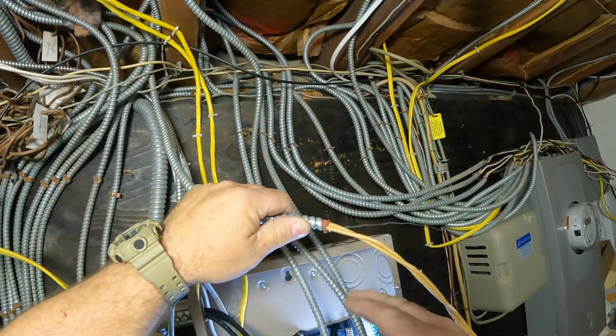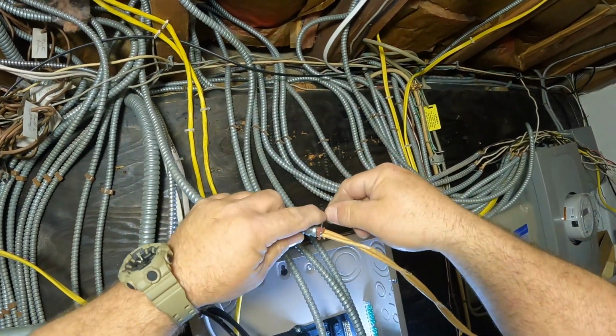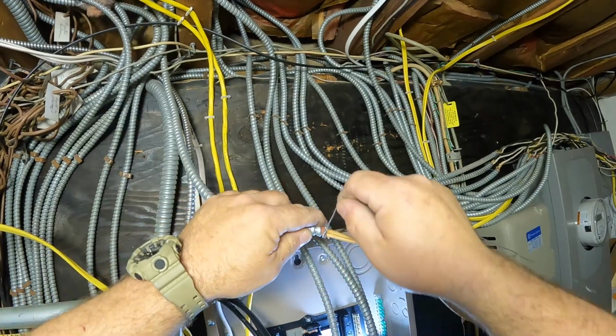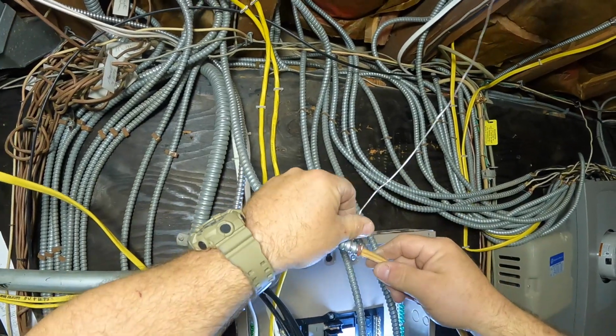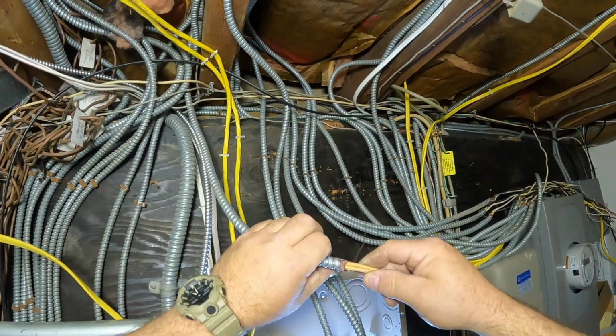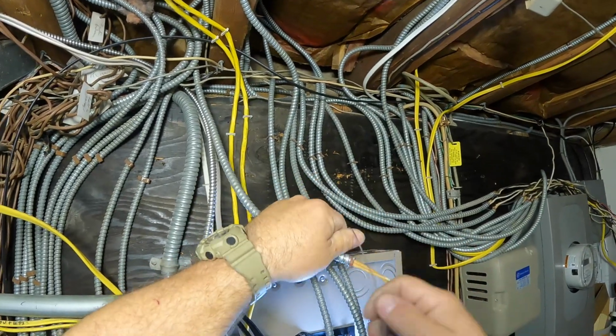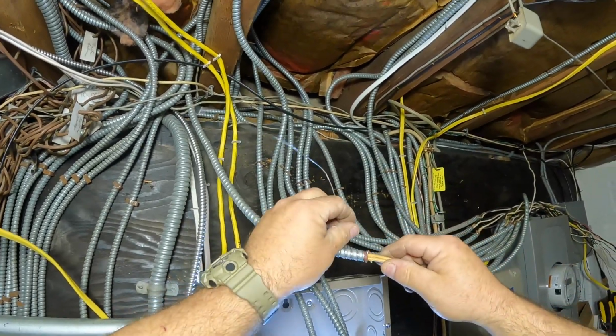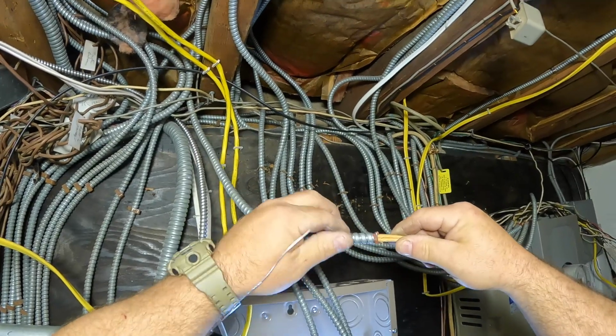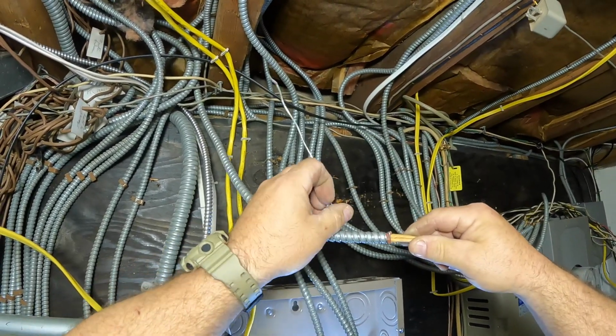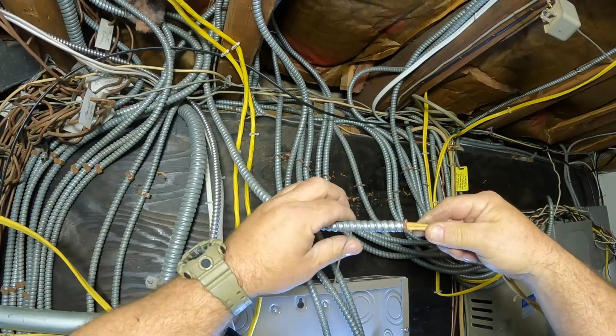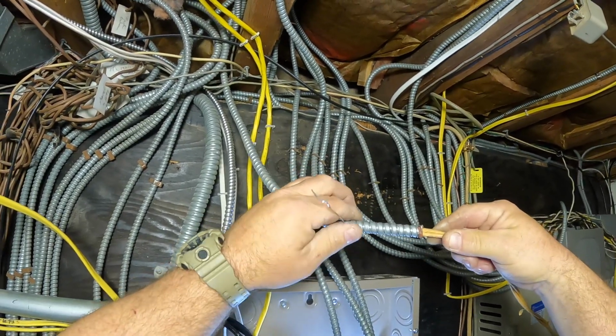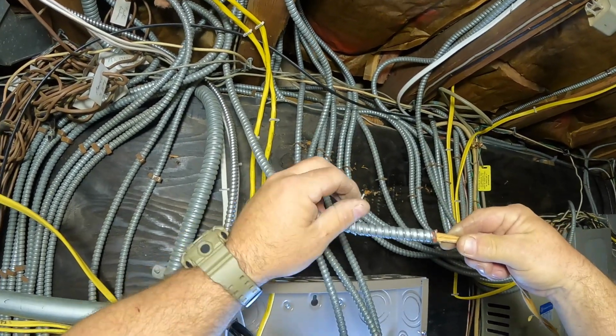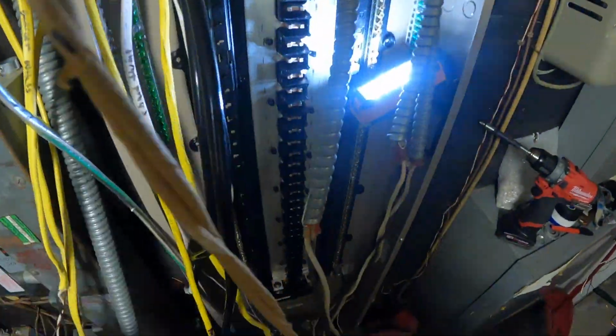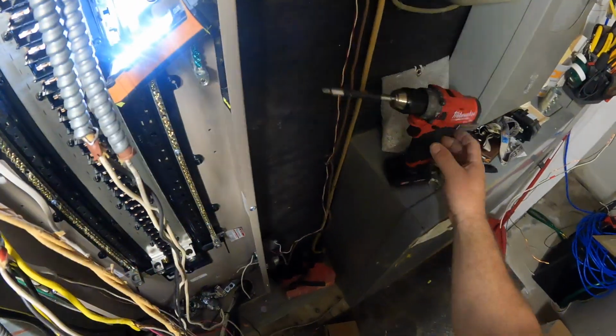So this one's a BX cable, and you see I'm putting what's known as a red head. The real term is an anti-short. And what that does is it safeguards the conductors from that sharp cut you just made with the cutters, from nicking the conductors. On armored cable, you are required to put the anti-short, aka the red head, around the conductors. For MC cable, it's not required, but I highly suggest that you put them in when you can.